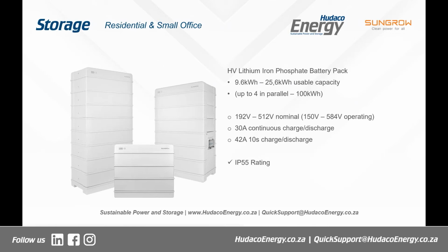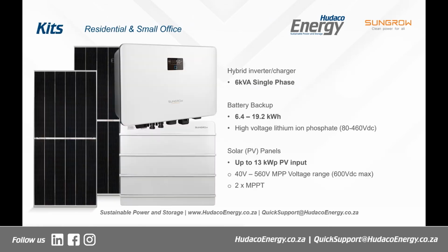The batteries are IP55 rated and the inverters are IP65 rated. In fact, the large grid tie inverters are IP66 rated as well, but even your residential stuff is 65 rated. In other words, you can put it outside. If it gets wet from a hose pipe, no big problem. I wouldn't submerge it, but if it gets a little bit of rain or splash on it, you're good to go. Next, please.